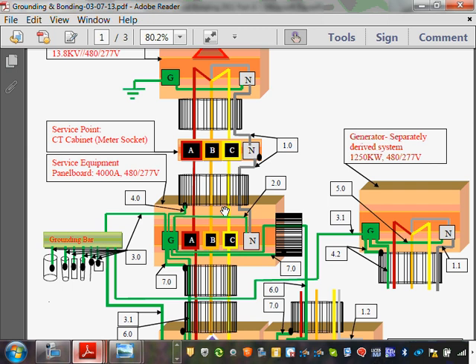Now what the code allows you to do too, also, they allow you to have a supplemental grounding electrode conductor right here. So if you want to go right next to the CT cabinet or termination box that you want to operate, and you want to drive another ground rod and tie it here, that's okay. You're allowed to do that one too. Not required, allowed, right in here. So this box is grounded through my neutral. Now I brought my rigid metal conduit into my building. I decided to use rigid, not PVC, for a reason. You're going to see why I've decided. Into an open bottom switch gear.